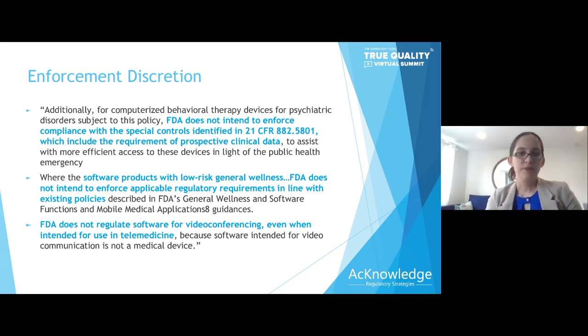To wrap up with this guidance document, I think this first bullet is the one that kind of blew a lot of minds. FDA does not intend to enforce compliance with the special controls identified in product code PWE, or under that regulation 882.5801, which includes the requirement of prospective clinical data. So FDA is saying they don't need to see clinical data, or it's not a requirement that you follow that special control. I should say, they do not intend to enforce compliance.